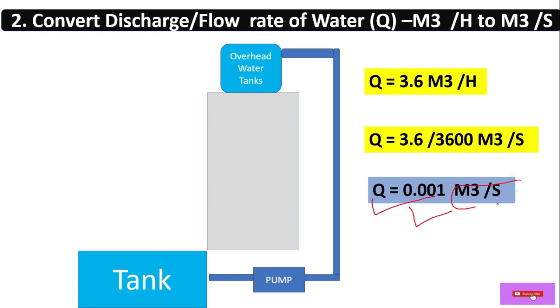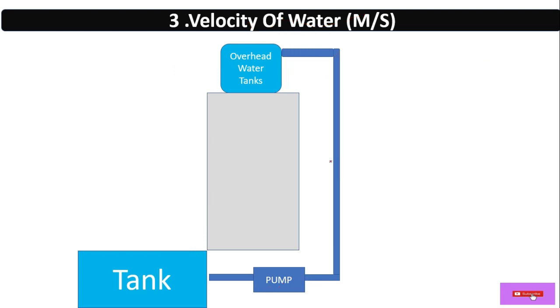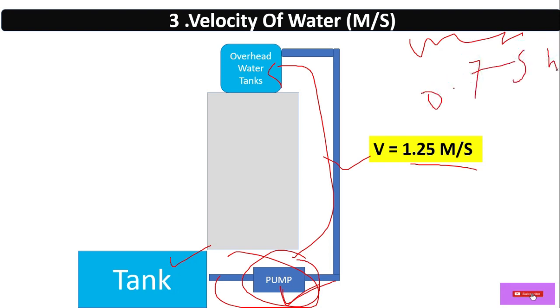In Step 3, we need to take the velocity of the water. There are two types of velocity: pressure velocity — when we transfer water with the help of a pump, we are providing pressure; and gravity velocity — when we distribute water by gravity. In this case we are transferring water from the underground tank to the overhead tank using a pump, so it is pressure velocity. The value of pressure velocity is 1.25 m/s; for gravity velocity we take 0.75 m/s.